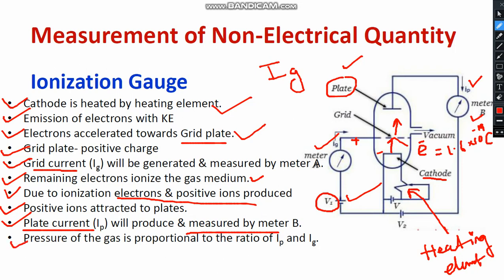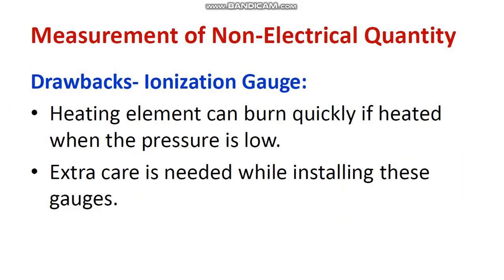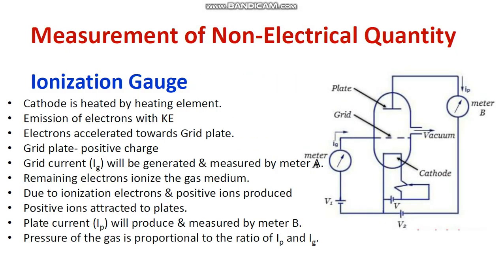The pressure of the gas is proportional to the ratio of ip to ig. Therefore, the pressure applied can be directly associated with the ratio of plate current to grid current: pressure ∝ ip / ig. This is the way the ionization gauge operates. To summarize: first, the grid current ig is generated; afterwards, the plate current ip is generated; and finally, pressure is directly proportional to the ratio of ip and ig.